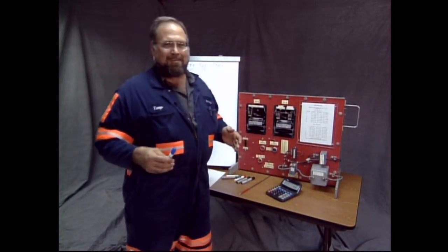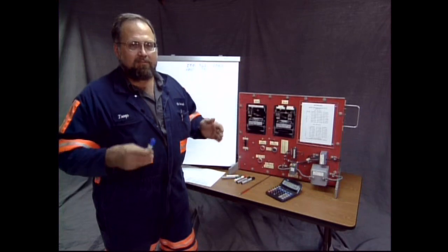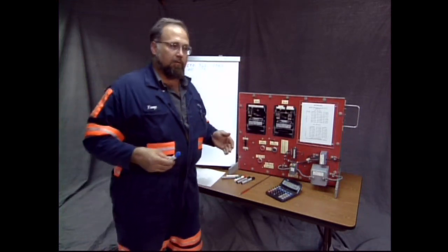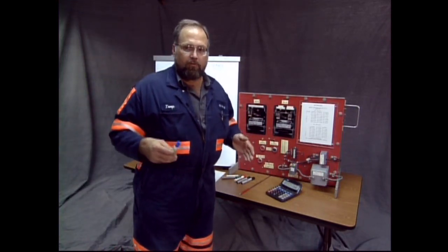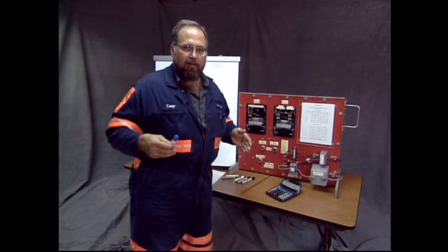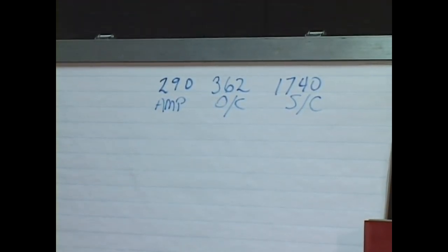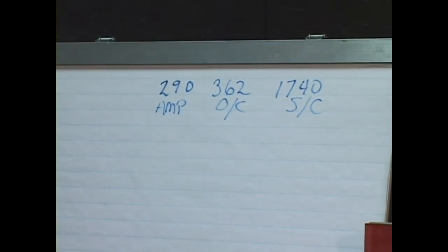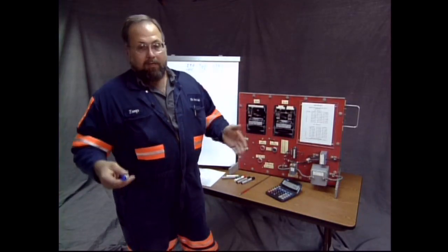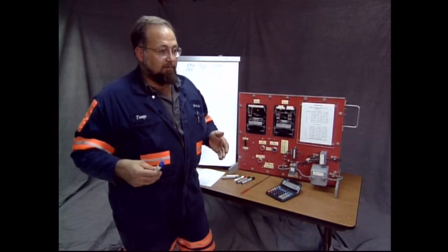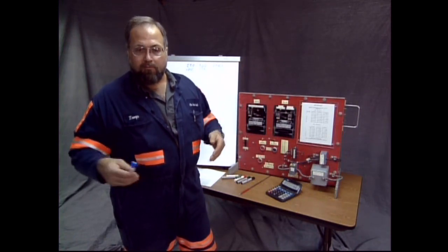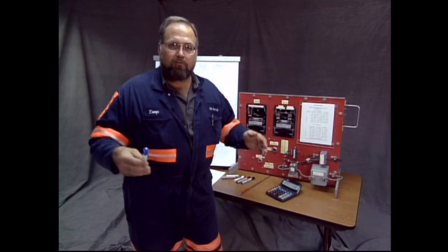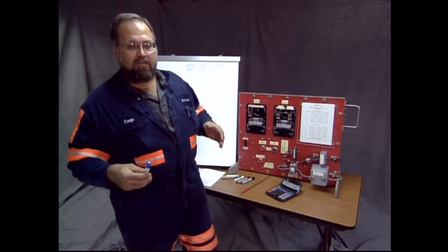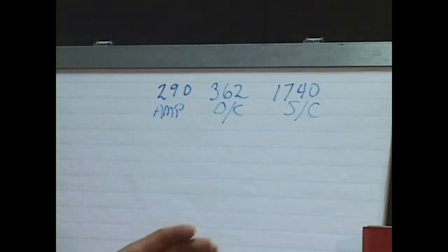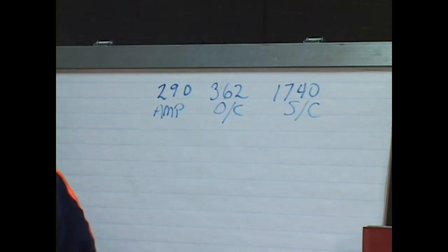Now, you don't want to maximize these levels. You can't have it tripping every few minutes, obviously, but you don't want to really challenge this cable. I'm going to set it at the max tap. Overcurrent, that's more or less your monthly budget. Your monthly budget, you have to pay. Some of us have mortgages and power bill and gas bill and telephone, telecable, all these different monthly expenses. That's your monthly budget. That's the one you're going to live under. This is going to be your day-to-day activity. How you run will be controlled by your overcurrent setting.